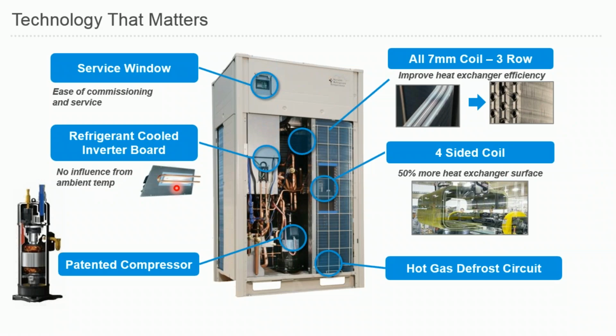The inverter board operation will still happen with refrigerant cooling. So your inverter board operation is not affected by the outside temperature changes and fluctuations, and we're still giving you maximum reliability on that end as well. A service window will be a standard feature with the new 4X. It will make things much easier from a commissioning and servicing standpoint.